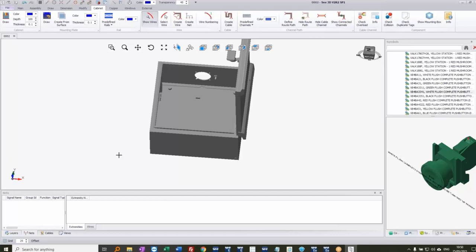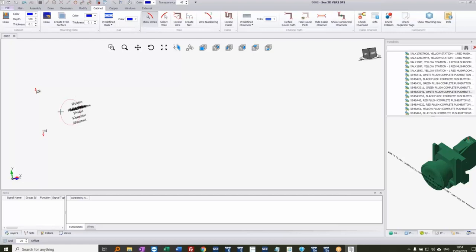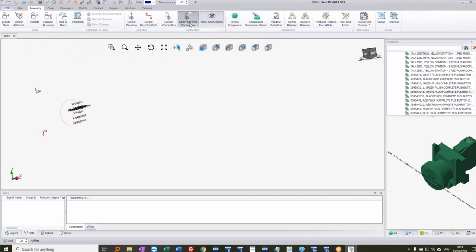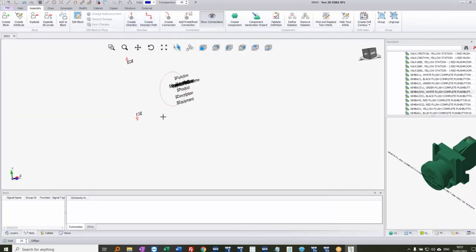There's a question about copying connection points and machining definitions from one part to another. If I right-click a push button symbol and explode it, I can delete all the graphical elements and be left with just the connection points, descriptions, and drill template — the drill hole. I could then copy those to the same position on another block. Alternatively, under Assembly there's an option to add connection points to any new symbol — you simply choose the connection direction and place it where needed.